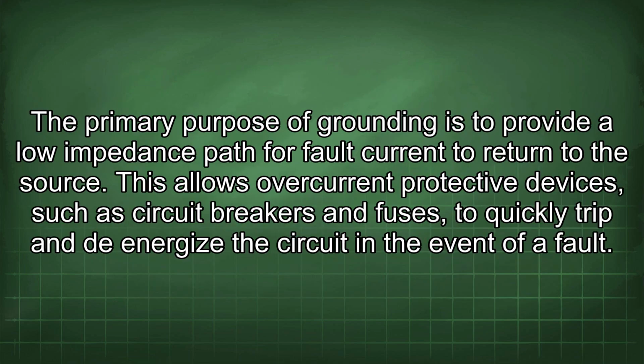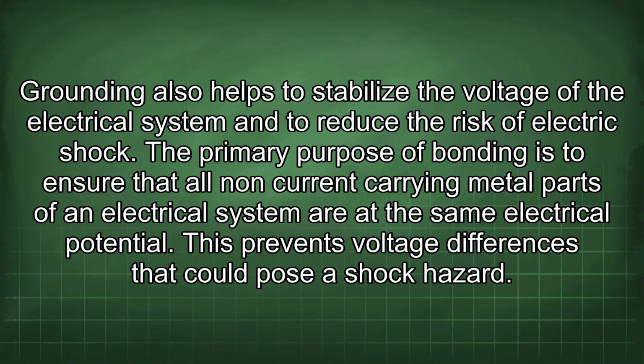The primary purpose of grounding is to provide a low impedance path for fault current to return to the source. This allows overcurrent protective devices, such as circuit breakers and fuses, to quickly trip and de-energize the circuit in the event of a fault. Grounding also helps to stabilize the voltage of the electrical system and to reduce the risk of electric shock. The primary purpose of bonding is to ensure that all non-current carrying metal parts of an electrical system are at the same electrical potential.